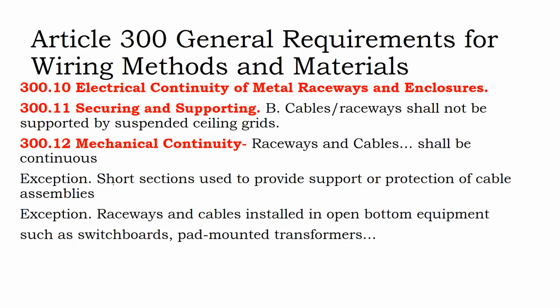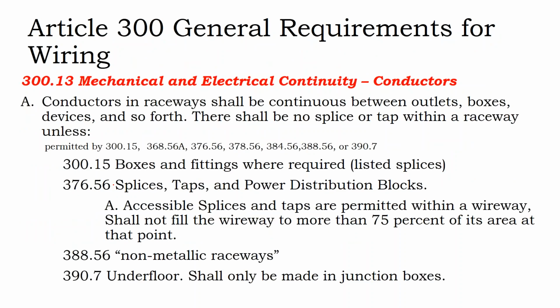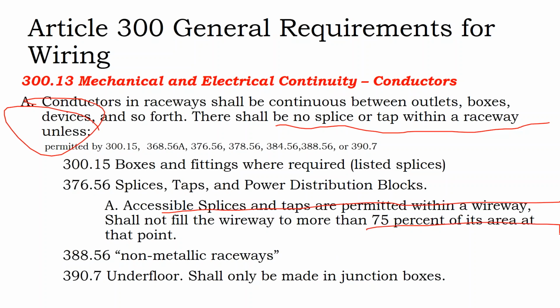Let's see, some of this stuff is kind of obvious, so we're just going to keep moving through. Conductors and raceways shall be continuous between outlets, boxes, and devices, and so forth. There should be no splice or tap within a raceway unless, and there are certain exceptions, one exception is you're permitted to do splicing provided that you're not filling up the wireway by more than 75% of its area.